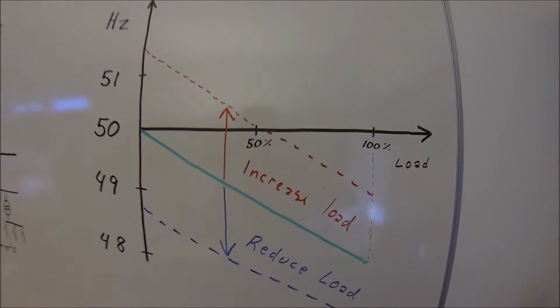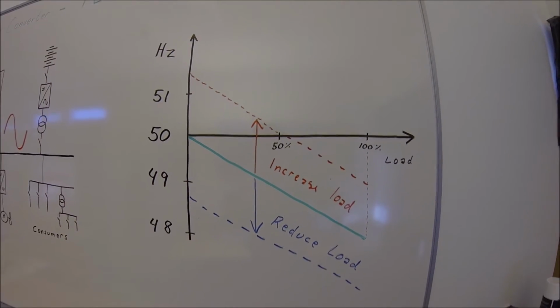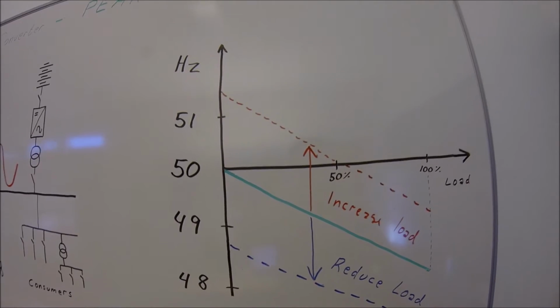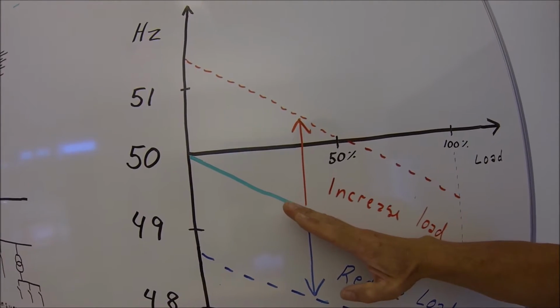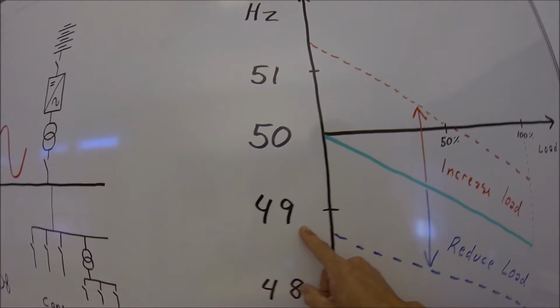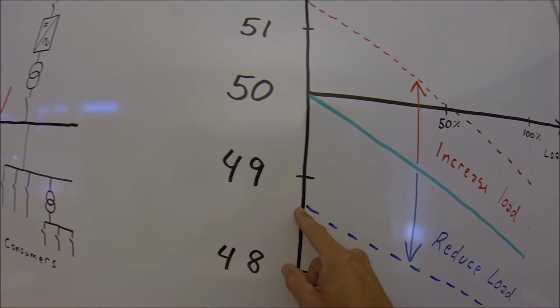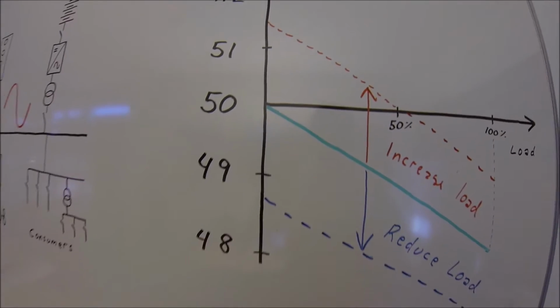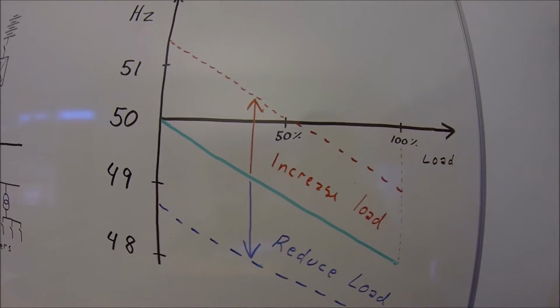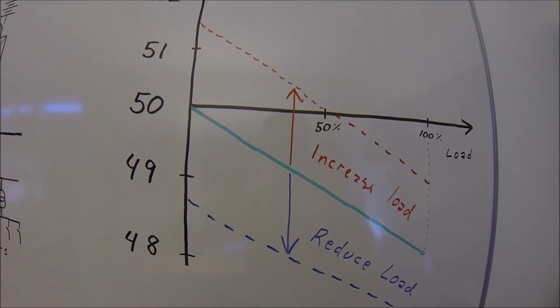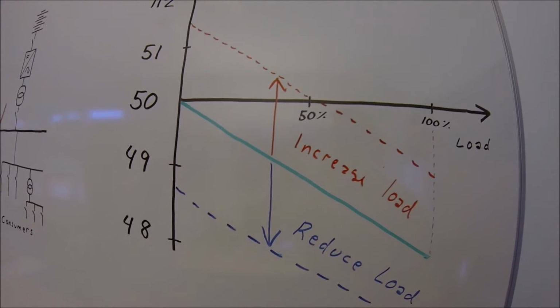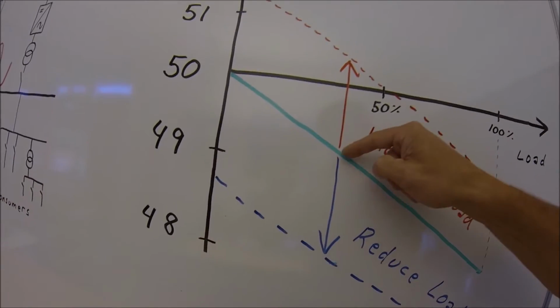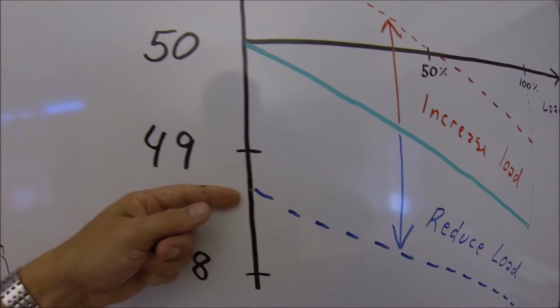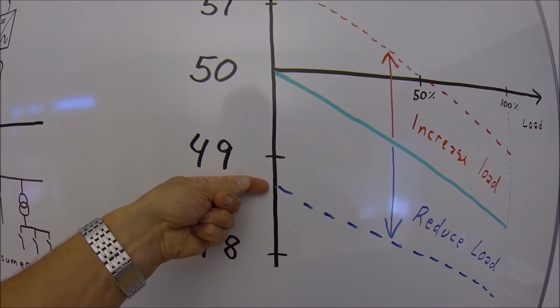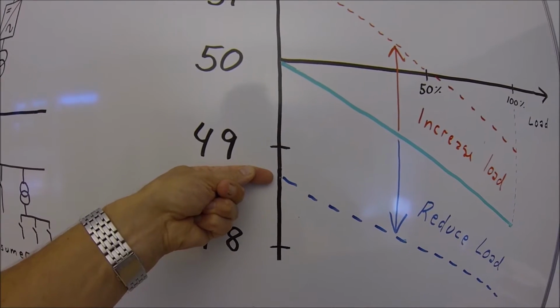If you look at the load diagram, the drooping diagram, it means that you basically adjust your curve. Let's say the grid has dropped to 48.7 hertz because of the load drooping on the ship. In isosynchronous mode, if you have told the drive not to take any load now, it will adjust down to this point. It will say that my base frequency now is 48.7. I don't take any load.